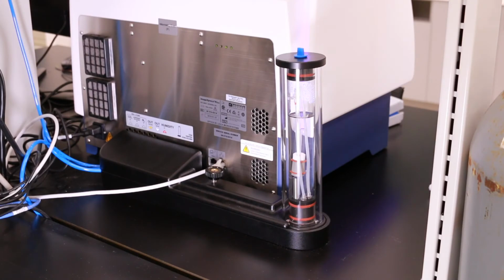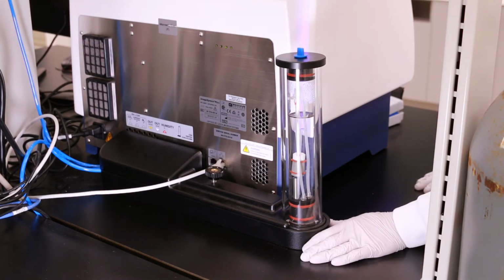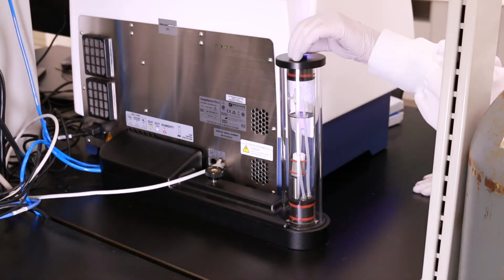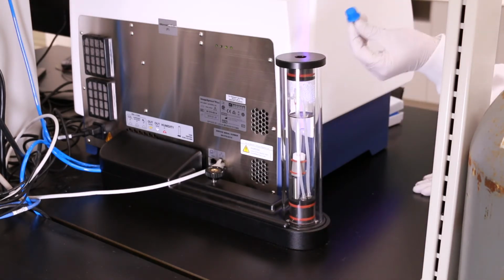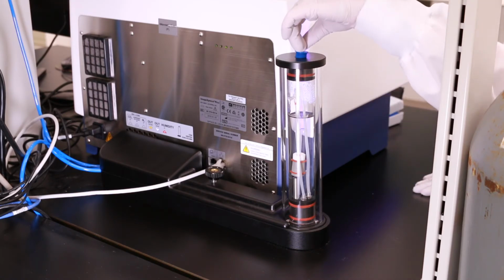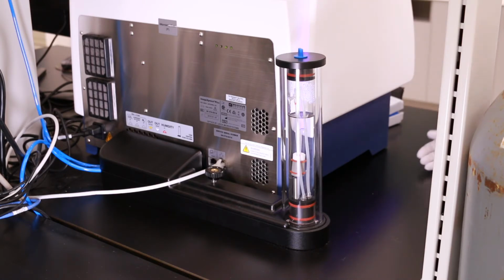You're also going to see a humidity column that's on the side that allows you to have your experiments at 85% humidity. One of the nice things about the ImageXpress Pico is that, as we said, it's a benchtop imaging system, and the environmental control fits within that benchtop space. So you can see here on the outside of the instrument, you've got the humidifying column. This allows you to have the humidity in the instrument at 85%. It also allows you to do longer time-lapse experiments by easily removing this plug and refilling the water when needed. So you don't have to stop your experiment. You can continue on running for multiple days at a time.